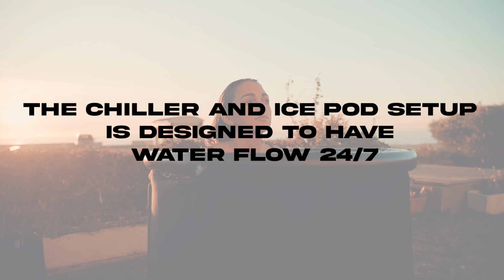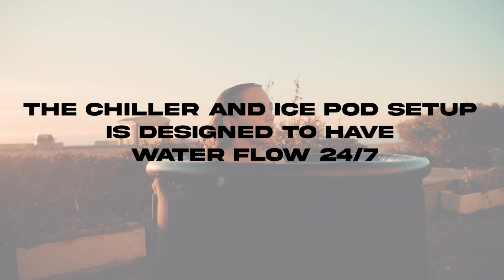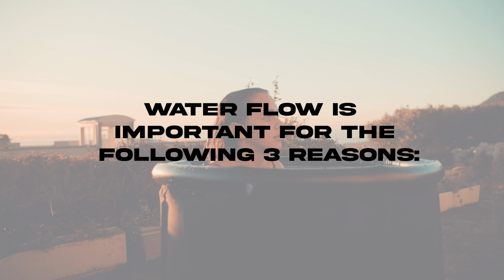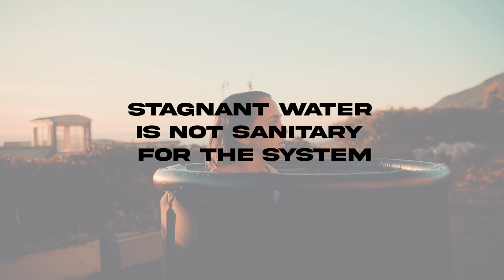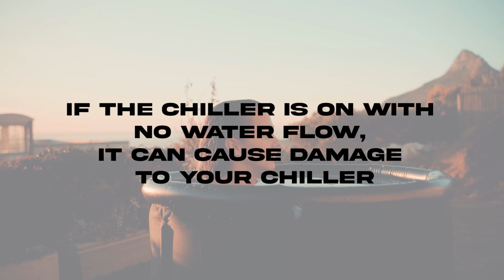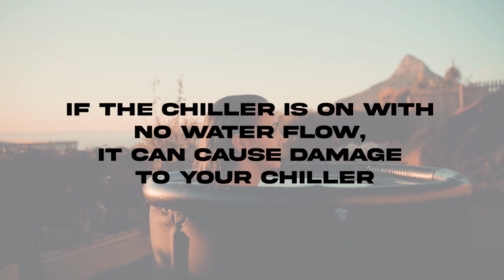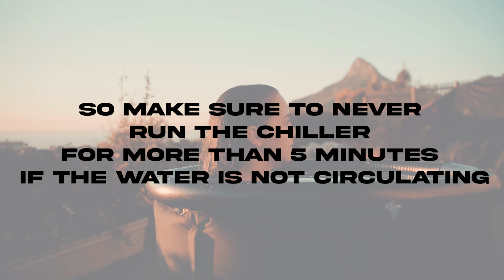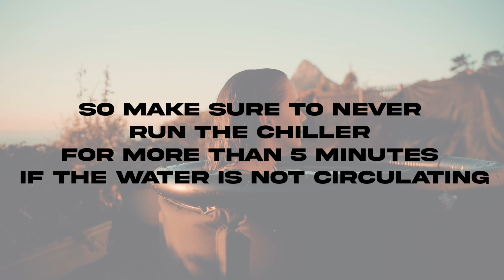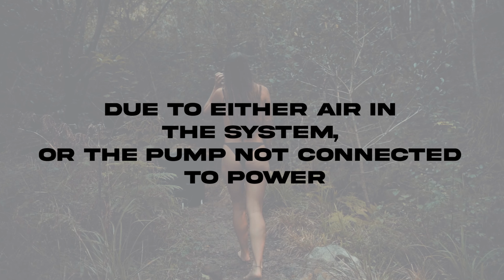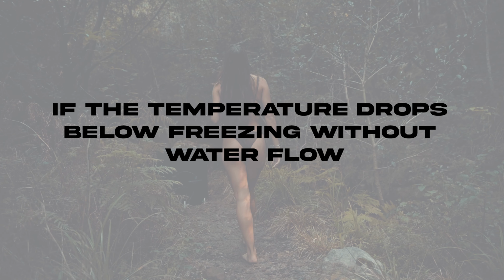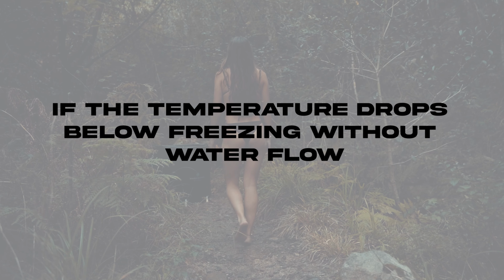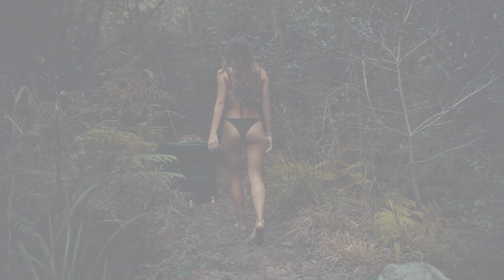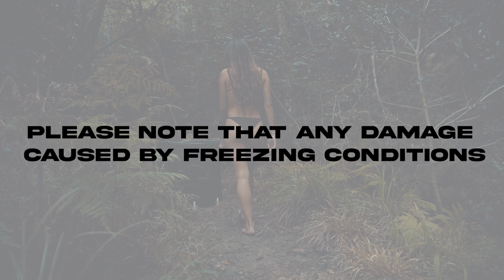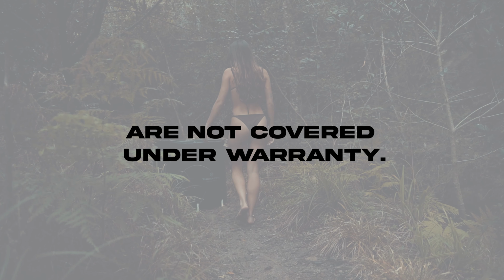Important considerations and warranty information. The chiller and ice pod setup's designed to have water flow 24/7. Water flow is important for the following 3 reasons. 1. Stagnant water is not sanitary for the system. 2. If the chiller's on with no water flow, it can cause damage to your chiller. So make sure to never run the chiller for more than 5 minutes if the water is not circulating due to either air in the system or the pump not connected to power. 3. If the temperature drops below freezing without water flow, it can ultimately crack the system. Please note that any damage caused by freezing conditions or improper water chemistry are not covered under warranty.